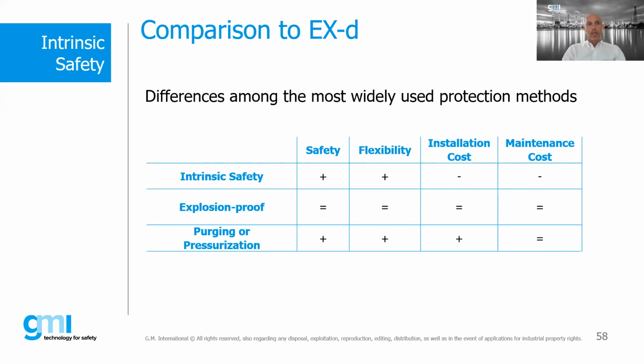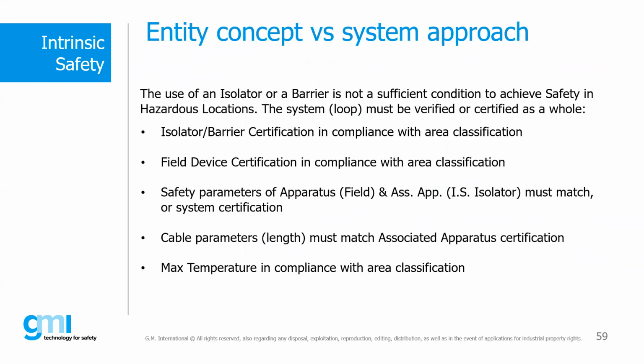So in terms of cost, installation and maintenance, and flexible safety, it has much more advantages than explosion proof. But I want to say also another thing: the use of an isolator barrier is not sufficient on its own to achieve safety in hazardous applications. So the total loop must be verified. The isolator barrier certification must be compliant with the ATEX classification.